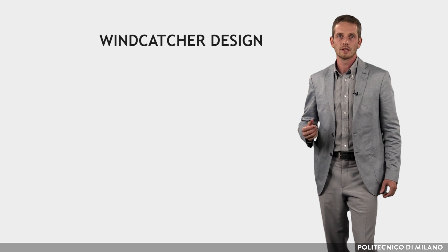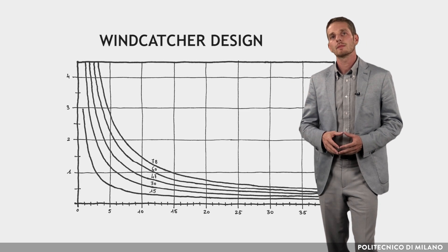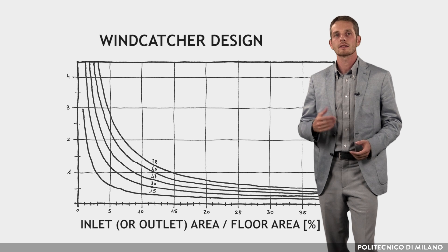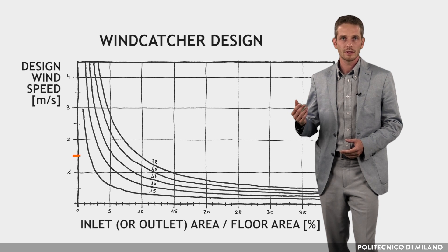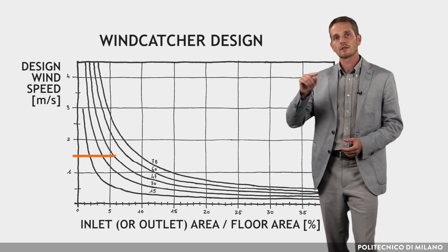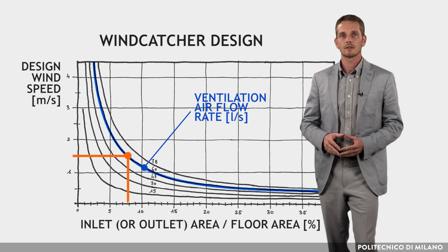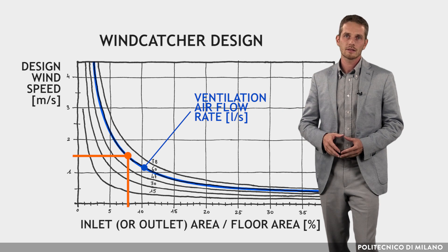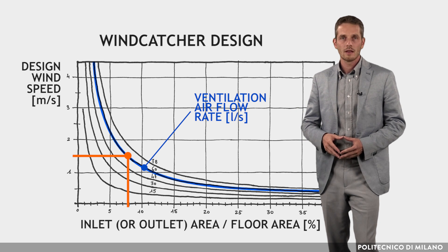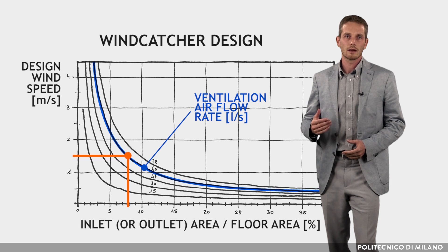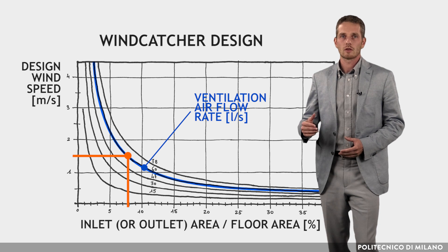When designing a new building, the size of the wind catcher opening required to achieve a given airflow rate can be determined from a graph as a percentage of floor area. As we can see here, one can enter the design wind speed on the vertical axis of the graph, move horizontally until the curve of the required ventilation airflow rate is intercepted, then drop to the horizontal axis to read the size of the inlet as a percentage of floor area. The graph is based on an incident wind angle of between 0 and 40 degrees to the wind catcher opening.